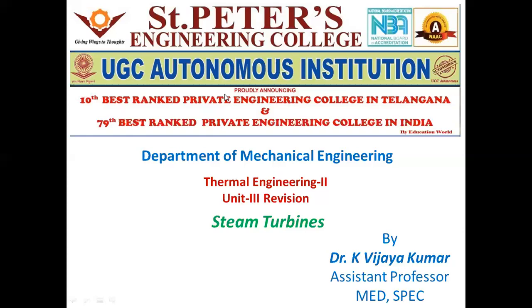According to the exhaust condition of steam, it is either a condensing turbine or a non-condensing turbine. In a condensing turbine, the steam at a pressure less than atmosphere is exhausted into the condenser, whereas in the non-condensing turbine, the pressure of exhaust steam is greater than the atmosphere. According to initial conditions, the turbine may be a low pressure turbine, high pressure turbine, or medium pressure turbine. It depends on the range of the pressure in between.